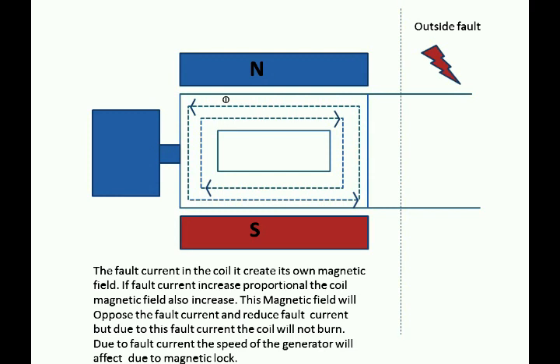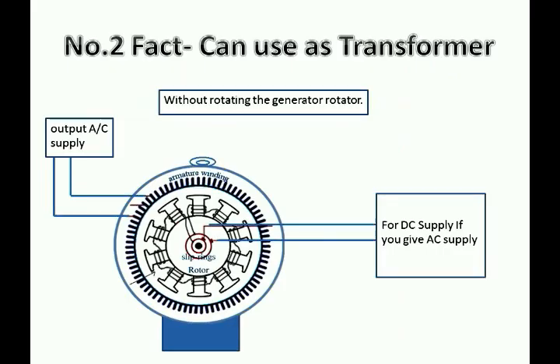Second interesting thing: we can use some generators as a transformer. In a generator, normally we give DC supply for the excitation winding. But in this case, if we give AC supply to the excitation winding and the rotor does not rotate, the generator output will produce EMF by mutual induction, like a transformer.